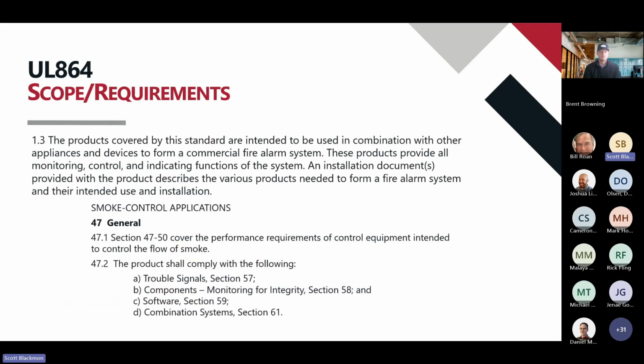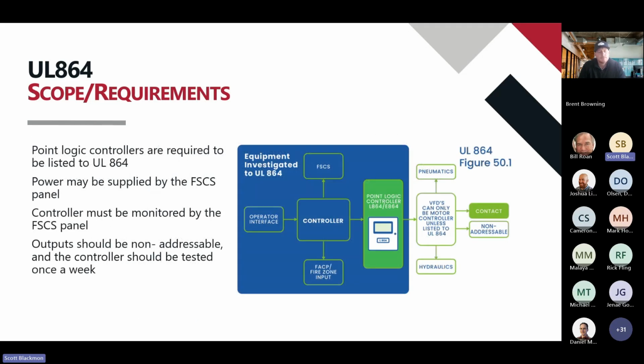So when we look at UL 864, more specifically chapter 47, we can see a lot of different things that UL starts calling out. They call out for the communication, for the backups, for the wiring, for all kinds of different applications. And what it boils down to is basically everything inside this blue box is supposed to be listed to UL 864. Now, if you'll notice, the VFD is sitting outside that blue box. So it's just a motor controller. It does not have to be listed to UL 864.